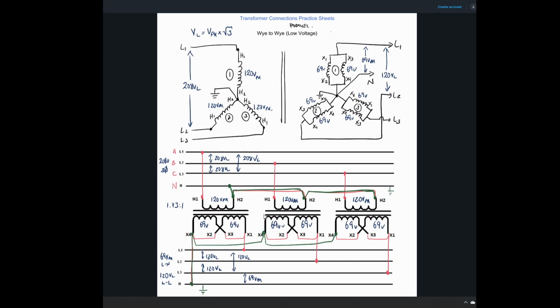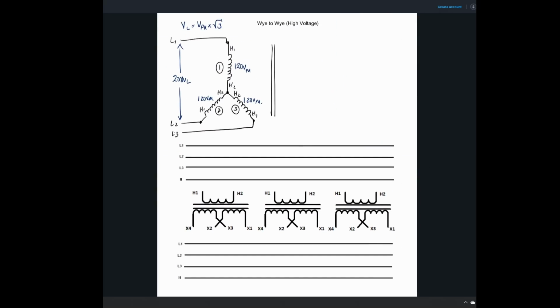But out in the field, you may have a 4-wire coming in and a 4-wire coming out. And both sides of the transformer, both the primary and the secondary, will be bonded to ground. And from my understanding, that's how the harmonics are transferred, because then you have a common connection, an electrically common connection between the primary and the secondary. So it's no longer just magnetic fields that are transferring from primary to secondary like you would have on the delta to Y. Now you've got a common connection on that ground where harmonics can then pass through this transformer. Okay, let's move on to the higher voltage now. Hopefully I didn't cause too much confusion there.